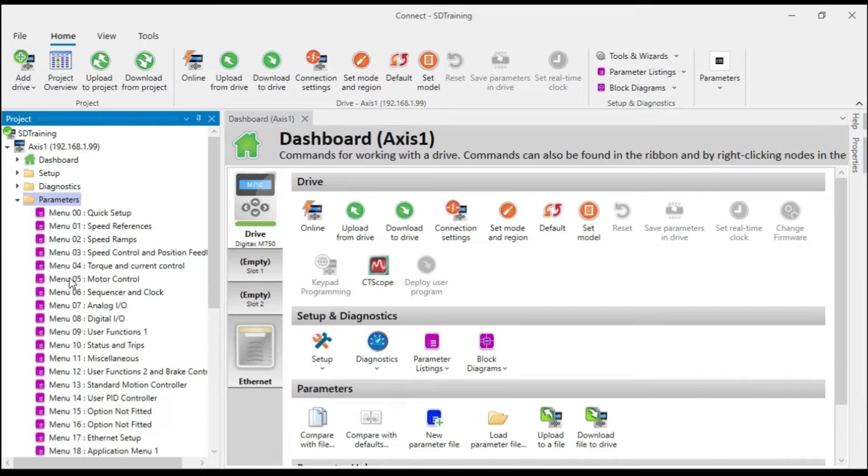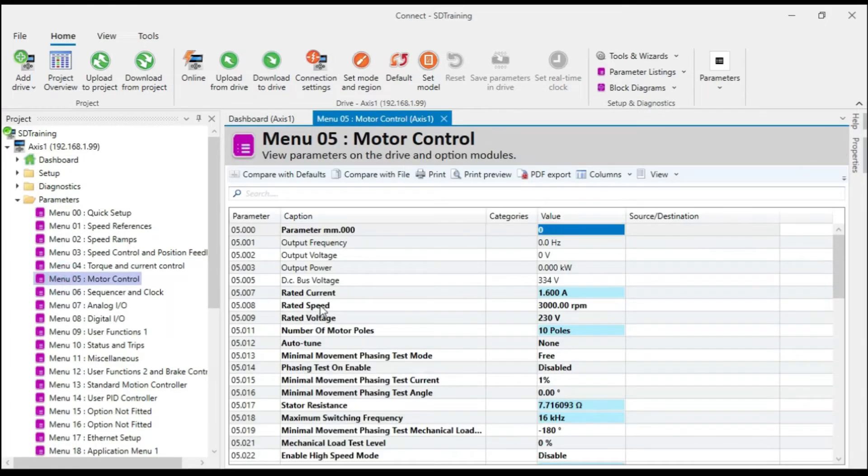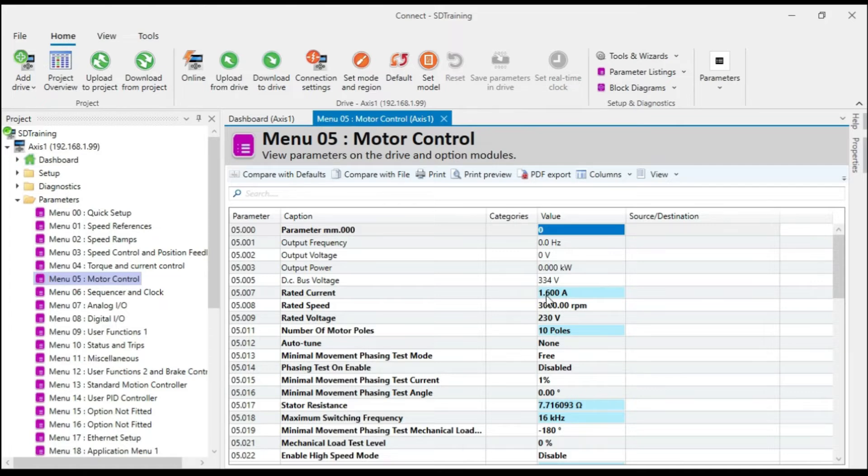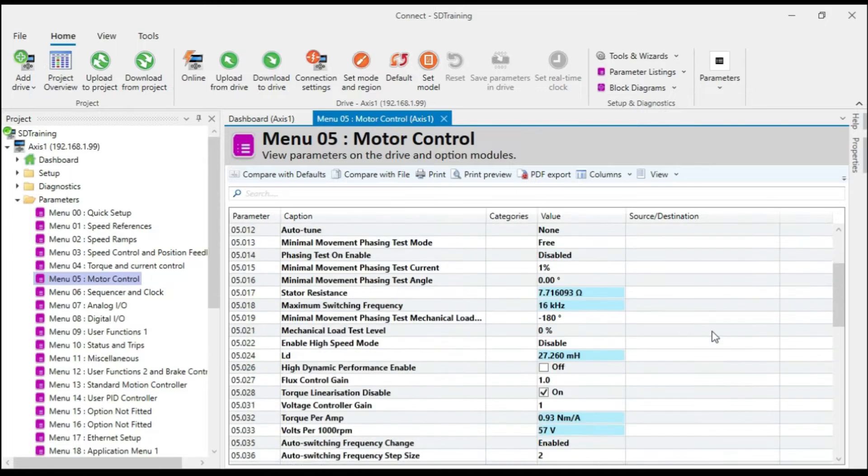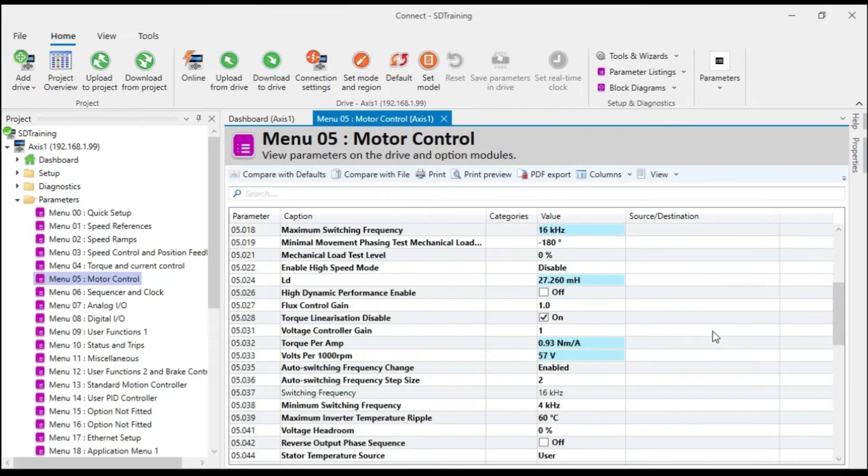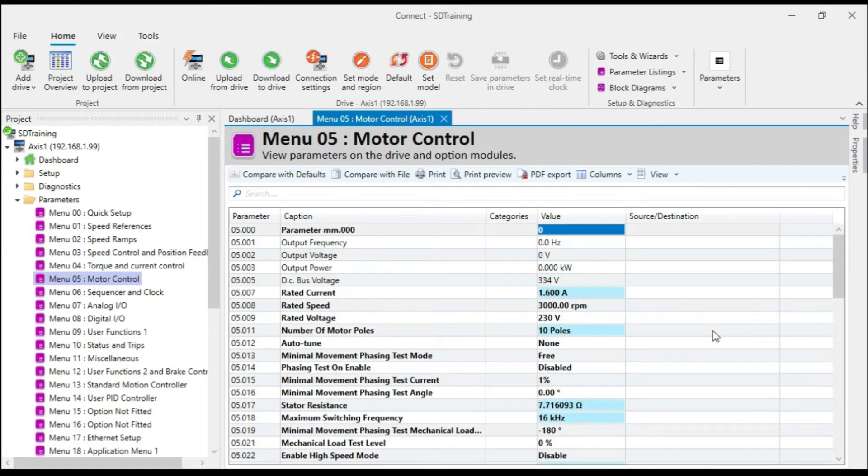And to illustrate that, let's look at menu five, which is where the motor parameters are. So as you can see, anything that's highlighted in light blue has been changed from default. So these are the actual motor settings for the motor that is connected to my drive.